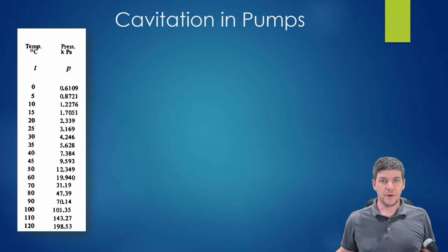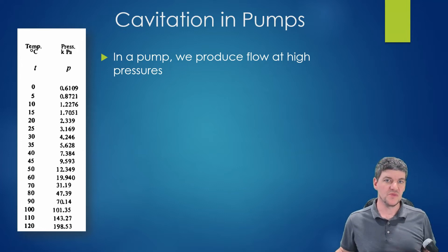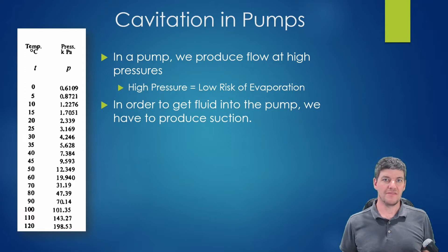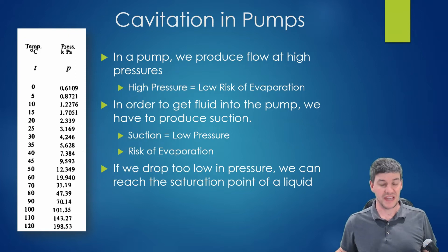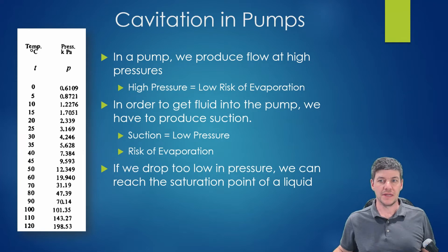Pumps are especially prone to cavitation. To move fluid and create high outlet pressures, a pump must also create suction, and the suction side is where the biggest risk of cavitation exists. Low pressure means high risk of evaporation and high risk of cavitation, so we have to be very careful that pressure doesn't drop too low inside our pumps.